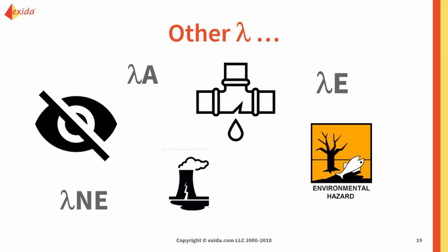Just like other failure categories, no effect failures can be further broken up into subclasses, but these aren't detected and undetected categories like the others. Because if they don't affect your safety system, why build a diagnostic looking for it? So you're not going to have any detected no effect failures. However, no effect failures can be classified into no effect or external leaks. And this will be extremely relevant if you have a hazardous process, something that could really do some damage if it is leaked out in contact with people or the environment.